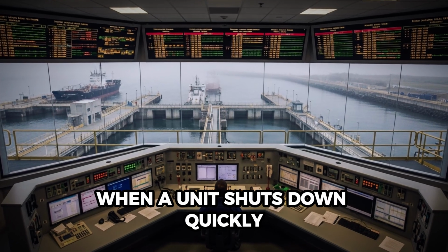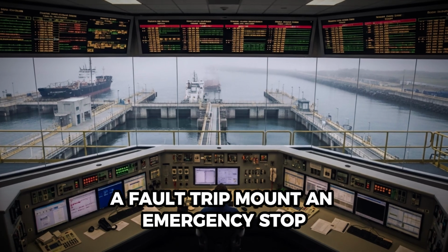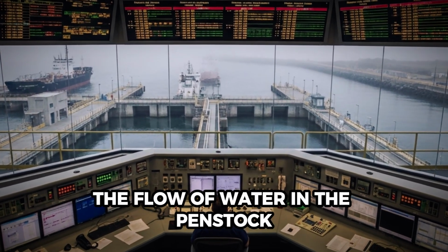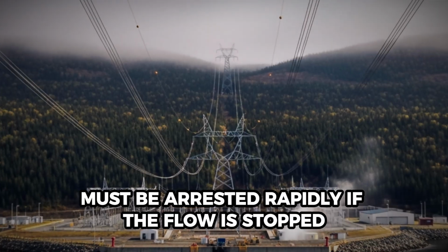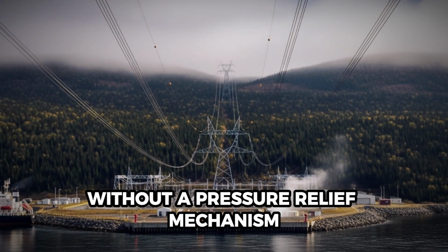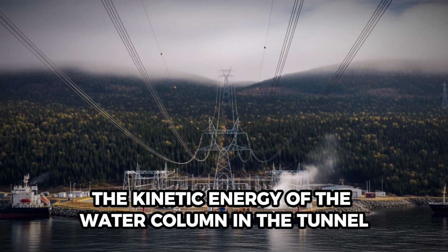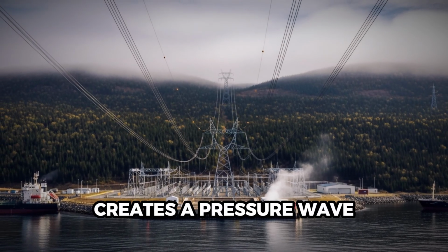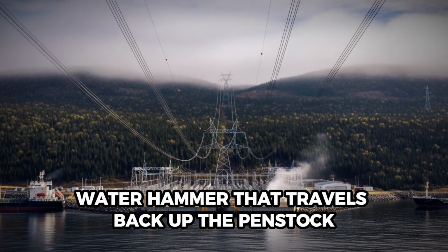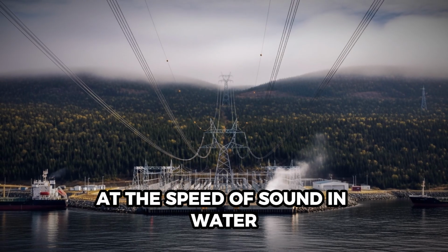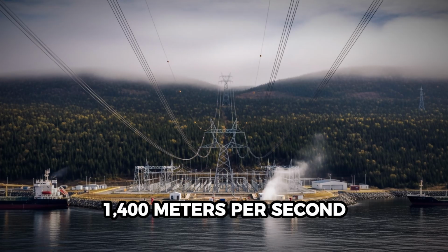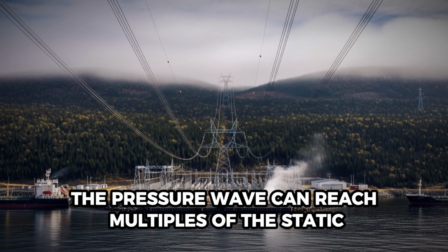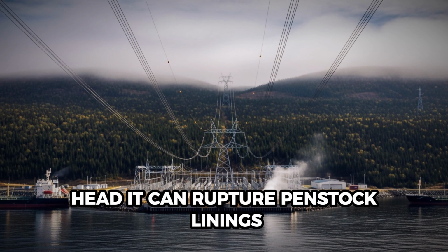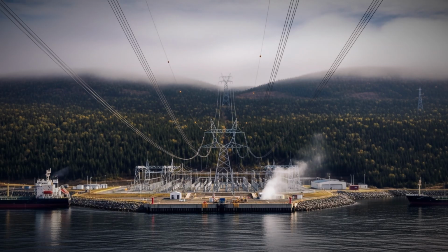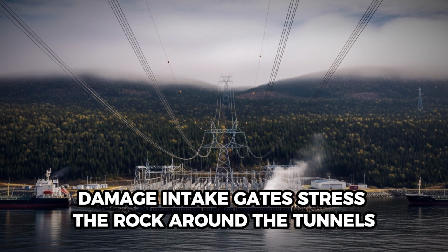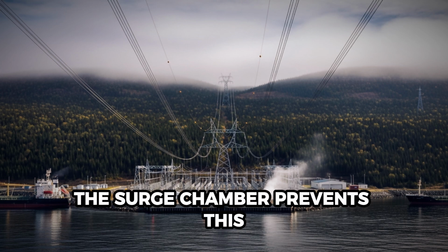When a unit shuts down quickly, a fault trip, not an emergency stop, the flow of water in the penstock must be arrested rapidly. If the flow is stopped without a pressure relief mechanism, the kinetic energy of the water column in the tunnel creates a pressure wave, water hammer, that travels back up the penstock at the speed of sound in water. 1,400 meters per second, the pressure wave can reach multiples of the static head. It can rupture penstock linings, damage intake gates, stress the rock around the tunnels. The surge chamber prevents this.